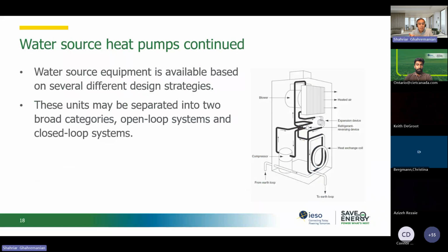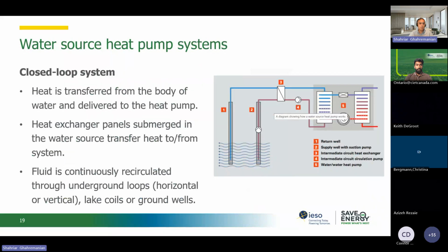I mean, there can be different solutions. The typical solutions for water source heat pumps are open loop systems or closed loop systems, and the preferred one is the closed loop system, because in the open loop, you have the flow of the water directly from the stream of water to your system, and that is not good, because then you need water treatment. So the preferred system is a closed loop system.